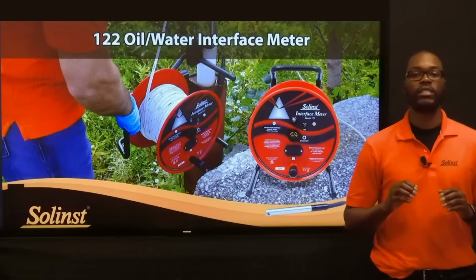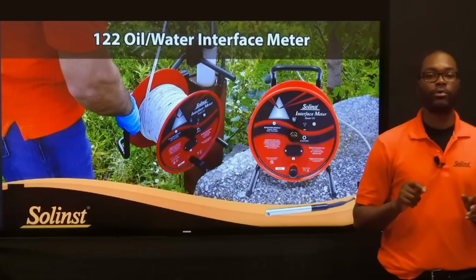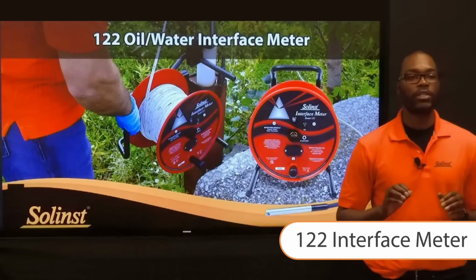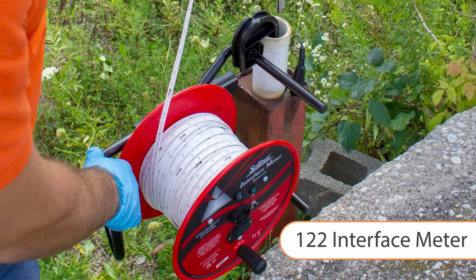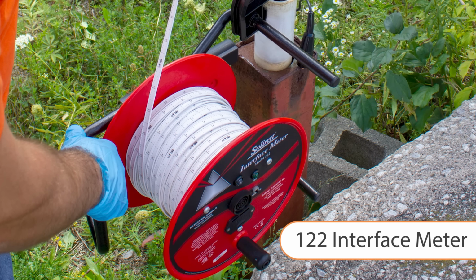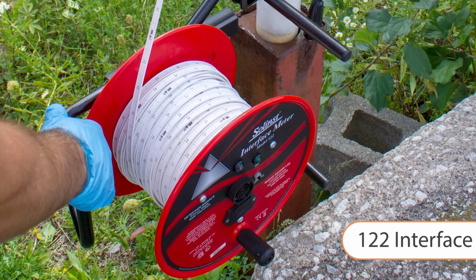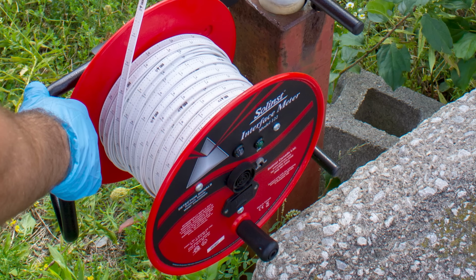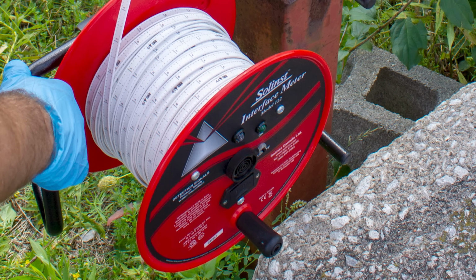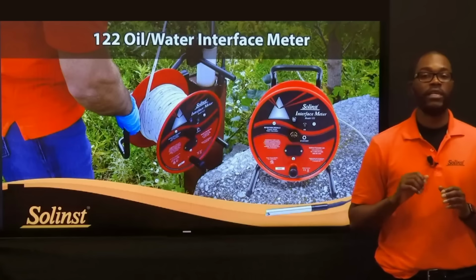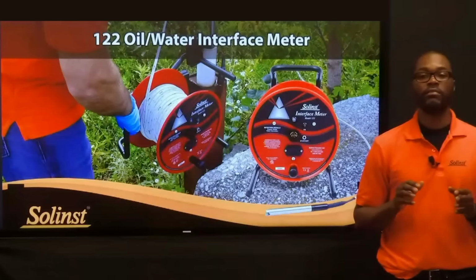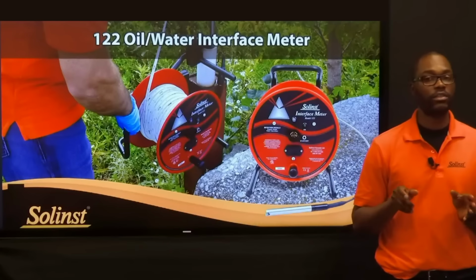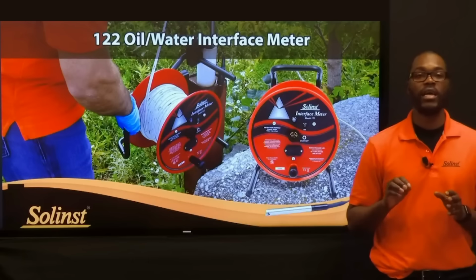Let's move on to other measurement devices which are designed to provide more water parameters and well measurement options. The Model 122 meter is the meter of choice when dealing with recording accurate oil-water interface measurements in harsh conditions. It is robust, accuracy is next to none, safe in hazardous environments. Our interface meters are CSA certified, intrinsically safe, and ATEX certified.